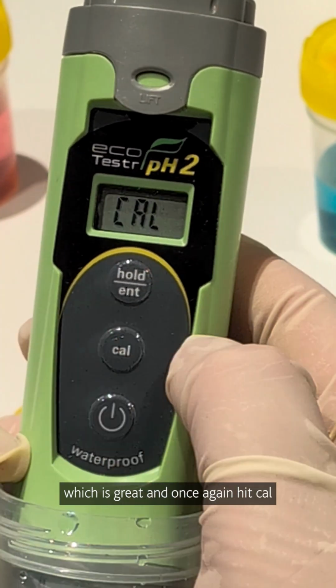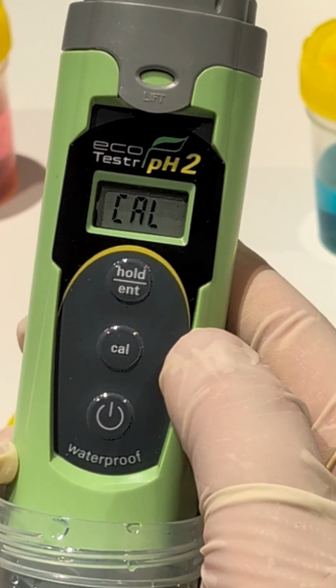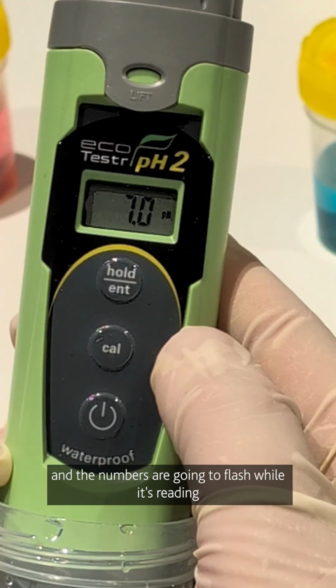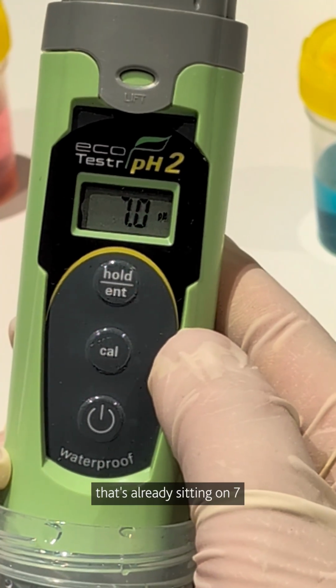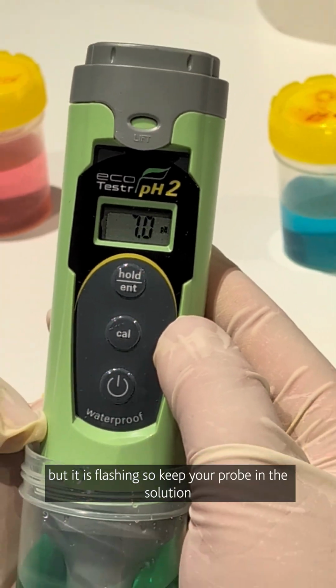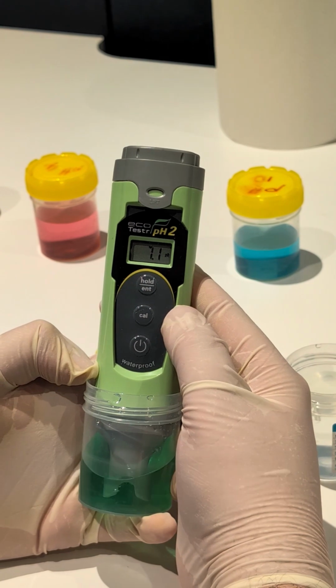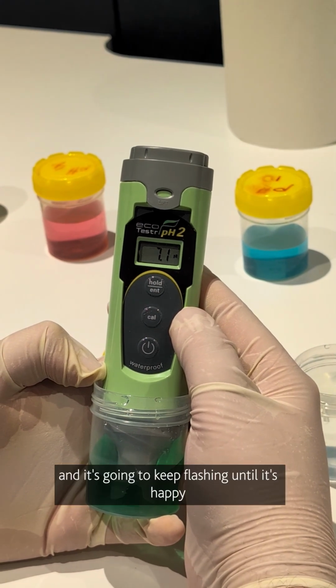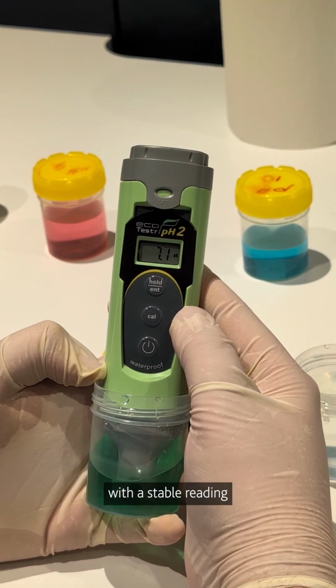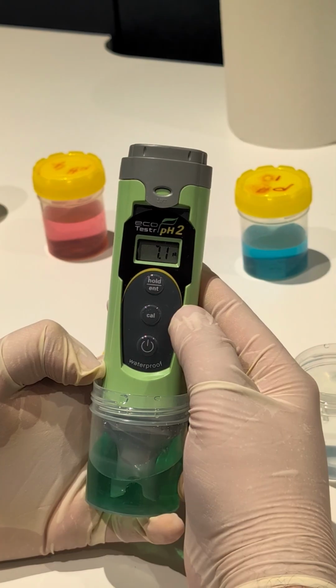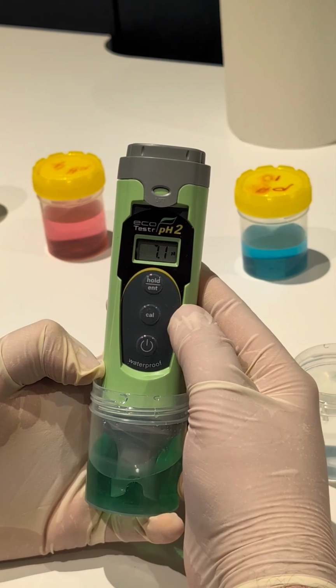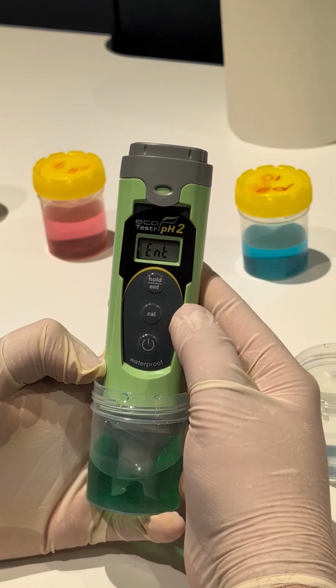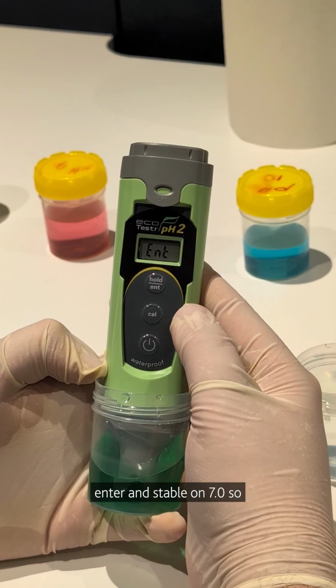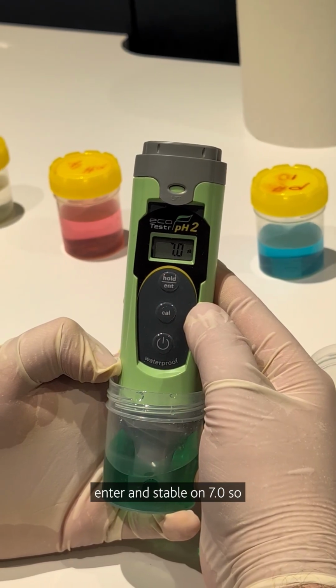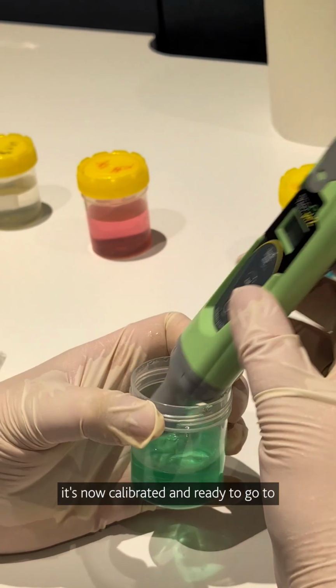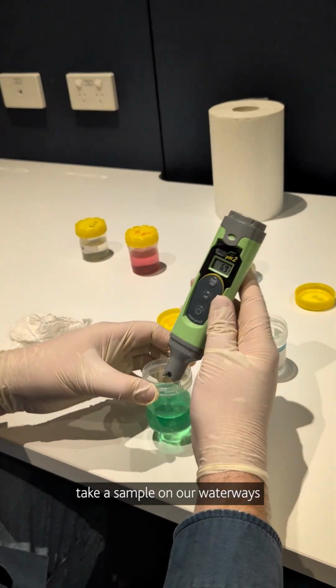And once again, hit cal, and the numbers are going to flash while it's reading. It's already sitting on 7, but it is flashing, so keep your probe in the solution. And it's going to keep flashing until it's happy with a stable reading. Enter, and stable on 7.0. So that's now calibrated and ready to go to take a sample on our waterways.